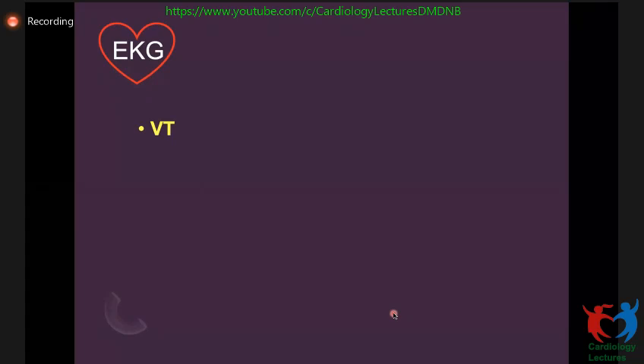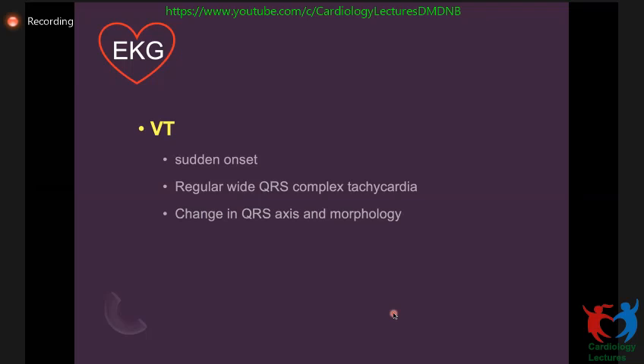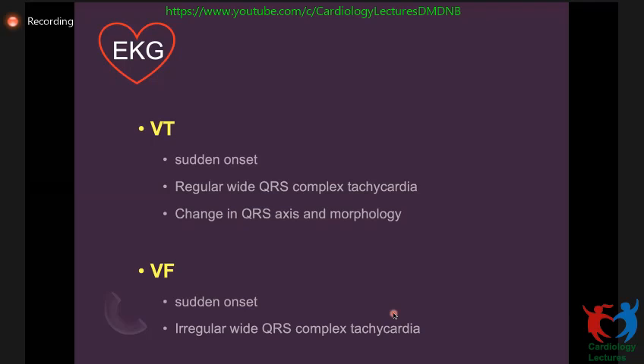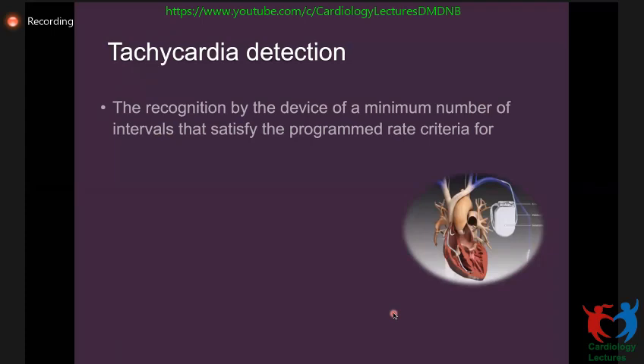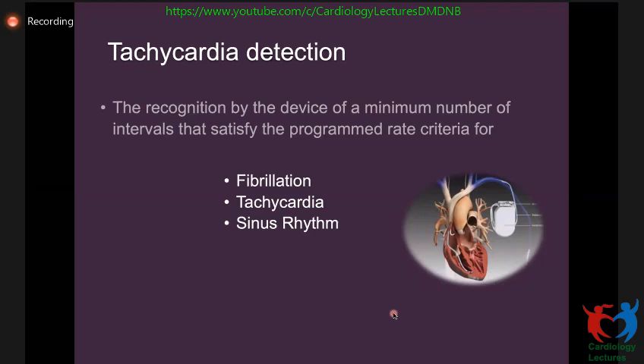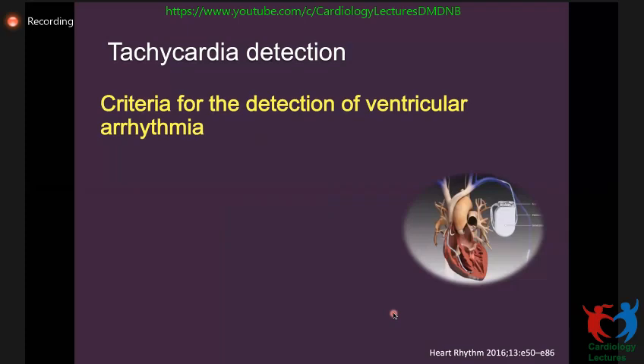For tachycardia detection, VT on EKG has sudden onset, regular wide QRS complex tachycardia, and abrupt change in QRS axis and morphology. VF also has sudden onset but irregular QRS complexes. The device needs to detect these features from the intracardiac EGM, distinguishing whether it's fibrillation, VT, or sinus rhythm. The ICD uses criteria including rate, duration, detection zones, and discrimination algorithms.